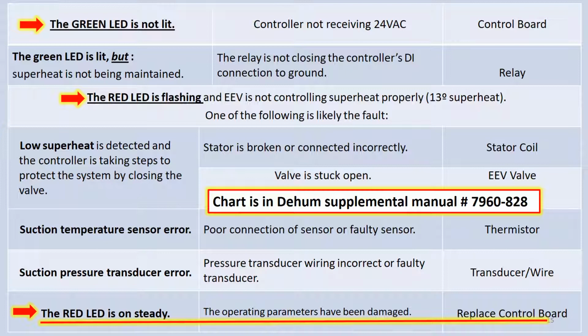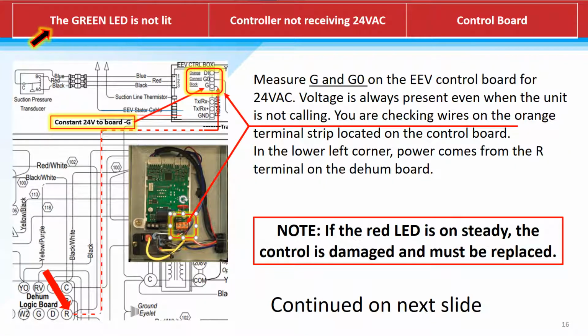We're going to use these lights and our meter to verify that the EEV system is operating. If the green LED is not lit, then we don't have 24 volts to the control board or it's defective. We need to measure on the orange terminal strip on that board between G and G0. If we have 24 volts present and the light is not on, we have a defective board. Remember, if the red LED is solid, the control is damaged and the board needs to be replaced.